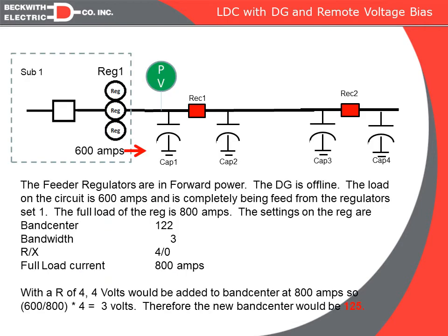The final topic is remote voltage bias, used mainly when line drop compensation is employed in conjunction with downstream distributed generation. Consider a feeder regulator with 600 amps of load and PV generation downstream that is currently offline. With a band center of 122, bandwidth of 3, R of 4, and full load of 800 amps, at 600 amps we apply 3 volts of compensation, setting the bus to 125 volts to keep the load center at 122. Then the DG comes online.